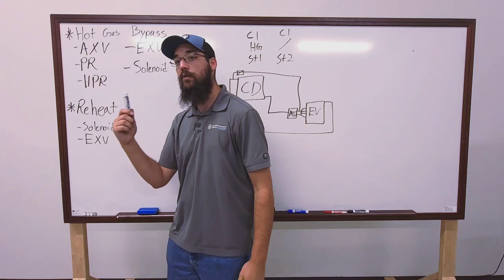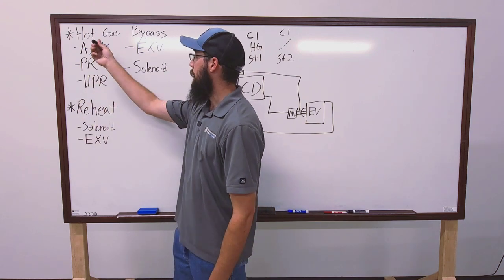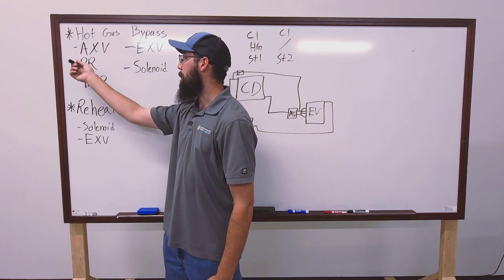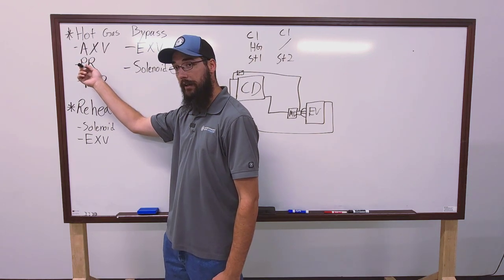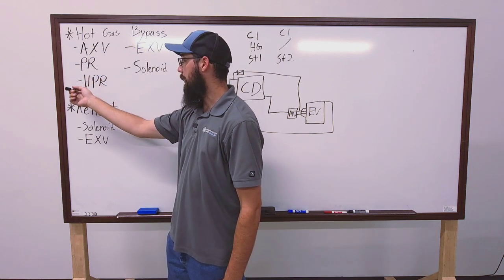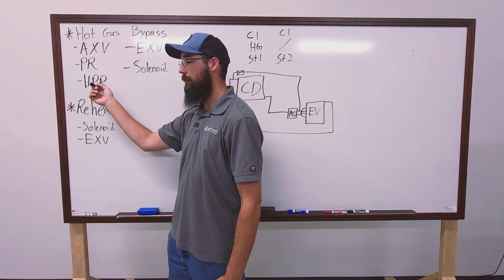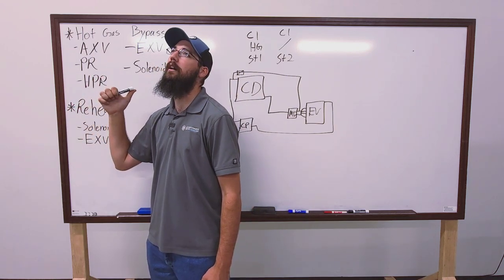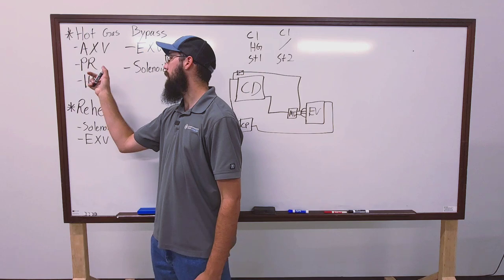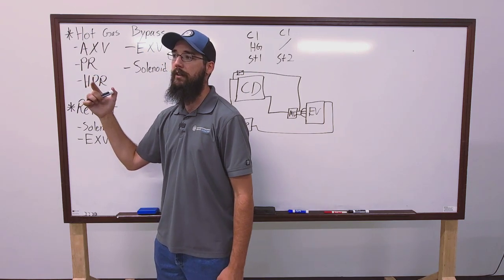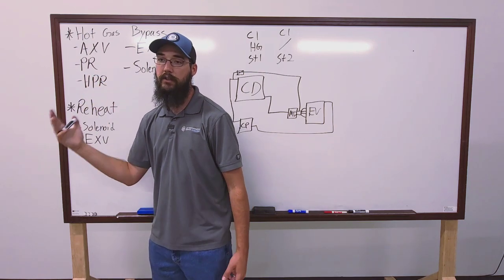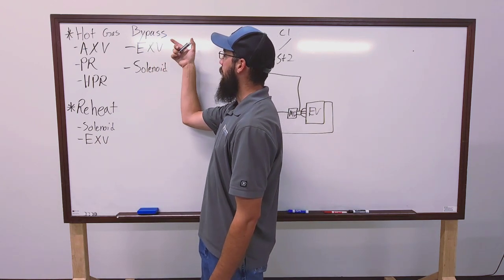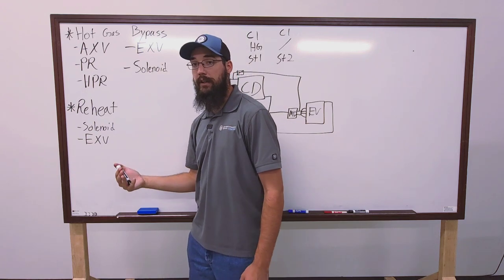Is the bypass typically just open-closed, like a solenoid, or is it more so like a step? So, that takes us into this list. There's several different ways it can be done. You have an AXV, which is an automatic expansion valve. You have a PR, which is a pressure regulator. An HPR, which is a head pressure regulator, also known as a head pressure control valve. I know them as HPRs. That's what I was trained on when I did low temp. And then you can have an actual EXV.